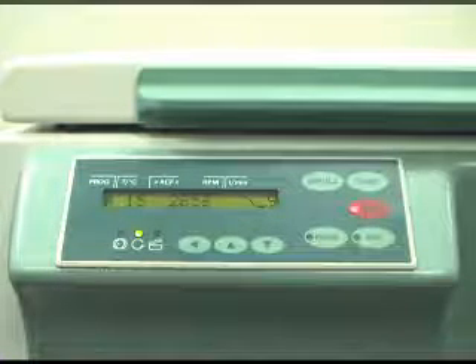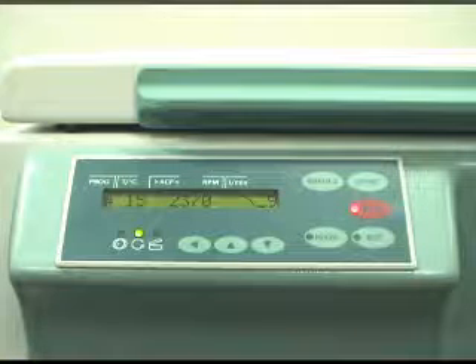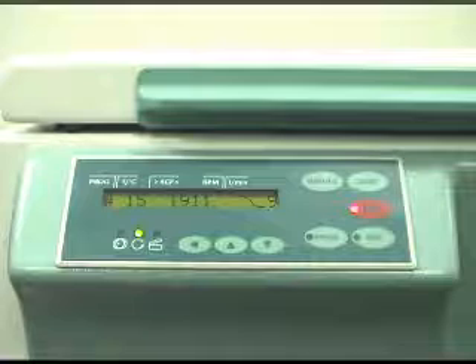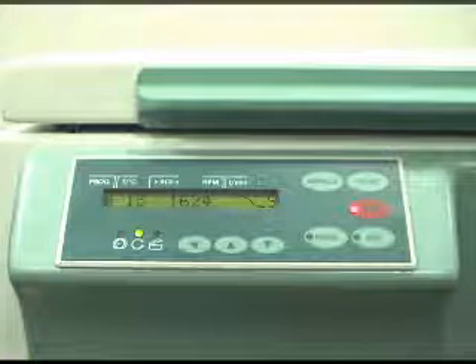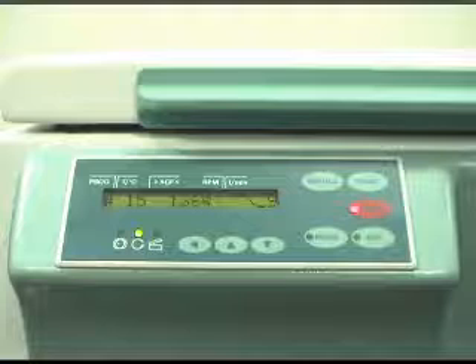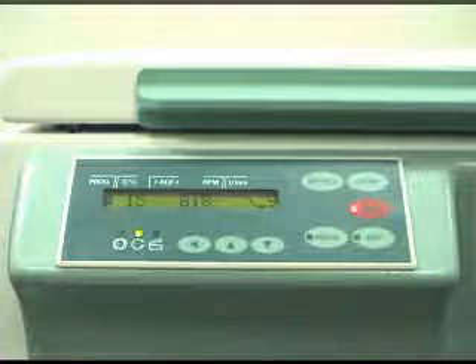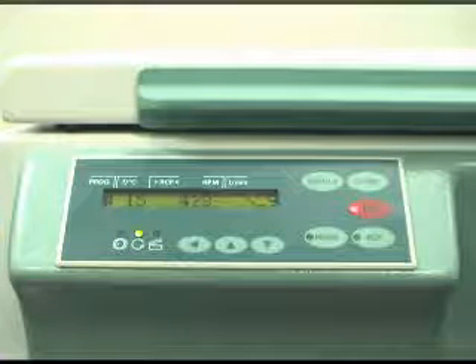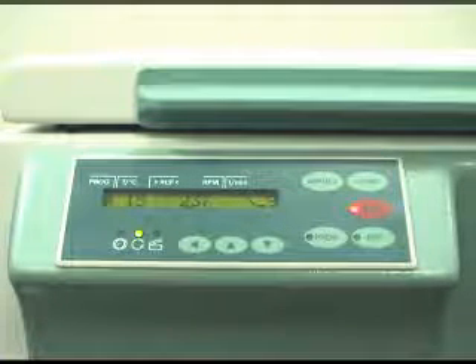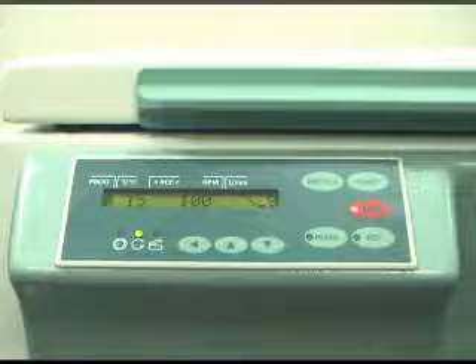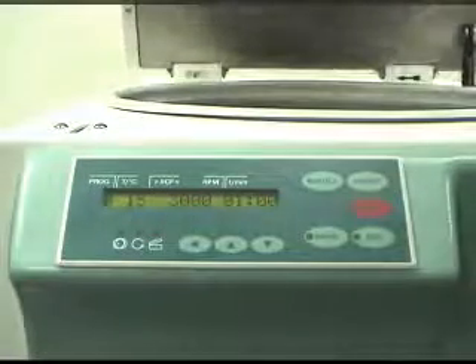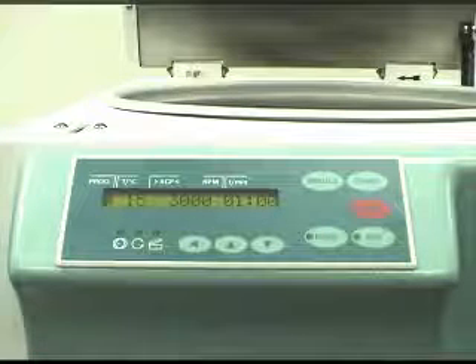Once the time is counted down to 0, the stop light comes on, the LED on the stop button, and the centrifuge spins down to 0. You can open the centrifuge now and see that it has come to a complete stop. If you've lubricated correctly, you should have a slight amount of spray of excess lubrication along the wall of the centrifuge. This is perfectly normal.